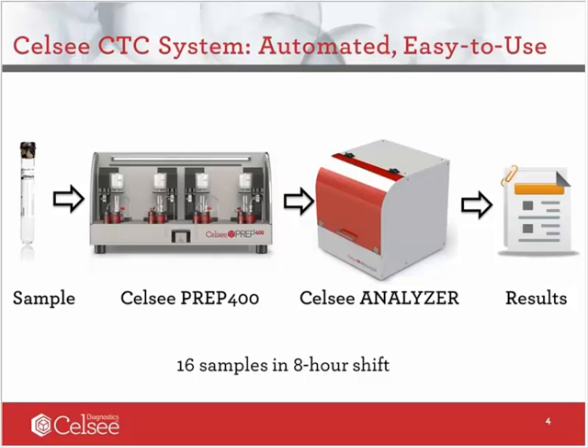Using this technology, we have developed an automated CTC preparation instrument called Celsee PREP400. As you can see on this slide, Celsee PREP400 has four modules, each with a pre-packaged reagent cartridge, allowing four blood samples to be processed simultaneously. The cell capturing process takes about two and a half hours. When the microfluidic chips are prepared, they are transferred to the second piece of instrument called the Celsee ANALYZER, which scans the whole slide.